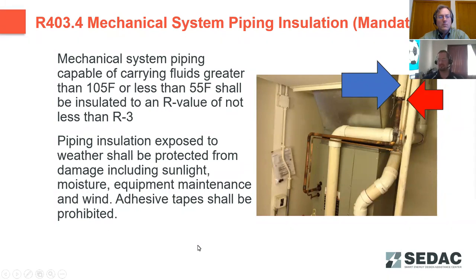When it's outside the house, it's not as much of an issue. It kind of acts like a pre-cooler for your AC condenser unit. But per code, all that refrigeration piping and hot suction line piping needs to be insulated. Another important component: if that is outside the envelope of the house and exposed to the weather, it needs to be protected from the elements, particularly mechanical damage and UV degradation. It's not uncommon to see that foam pipe wrap dry rot over time and flake off the lines, and then you don't have insulation anymore. There are UV protective wraps that can be added to the outside of that. There are also paint-on coatings that all add that UV compliance to that insulation.